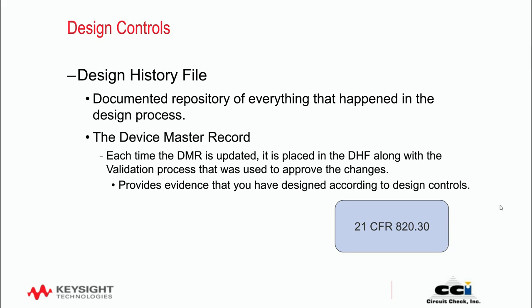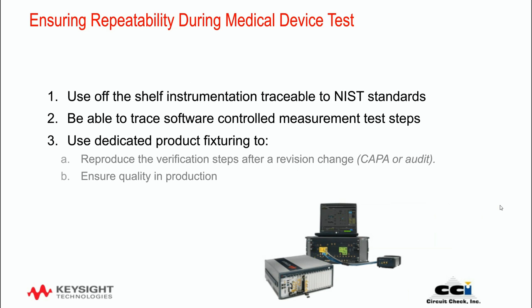As part of that design history file, you'll have a device master record. Each time the master record is updated due to a product revision, it's placed in the design history file. This is where you'll place everything you're doing regarding RF coexistence and all the test methods you've used in verifying and validating your device to its intended use. The design history file will document all of those tools and methods.